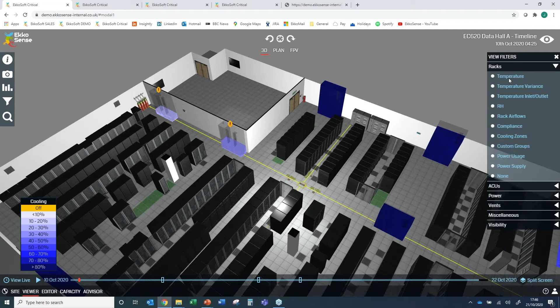In this example, these two exclamation marks above the units are highlighting poor performance of those rack units. These units haven't failed yet, so there's no BMS failure, but our algorithms show that these air conditioning units are not working as they should.